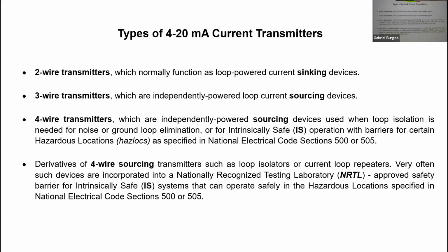They're giving you out energy, current. 4-wire transmitters are independently powered sourcing, but they're used when you need loop isolation. I'll show you that in a minute. The purpose of that is for noise, or for intrinsically safe operation with certain barriers in hazardous locations. The hazardous location is specified by the National Electrical Code, sections 500 and 505. Then there are derivatives of these which act as loop isolators or current loop repeaters. These are often included in the safety barriers.